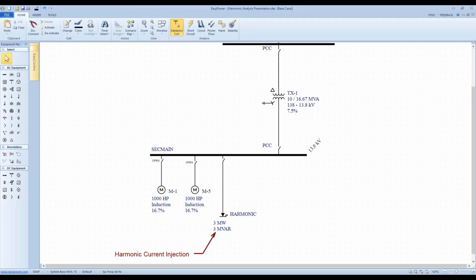That's a lot of work, and in the end, I don't really know what the value of that is, because these devices, when you have multiple devices on the same bus and they're operating at different speeds, different load levels, they are putting out harmonics that are at different phase angles, and the net result is that it's not completely additive. There is a degree of cancellation of those harmonics, and therefore putting a harmonic current injection associated with each load and every load on that bus may give you quite a pessimistic result. And doing a harmonics measurement at the point of common coupling might make more sense.